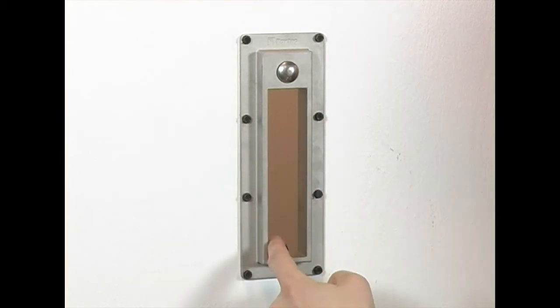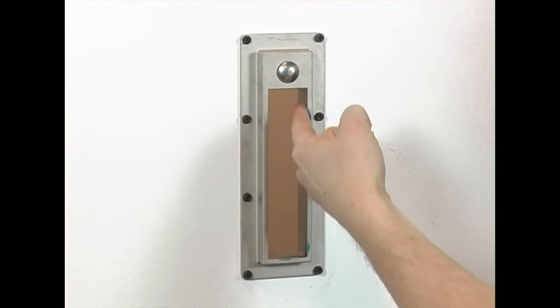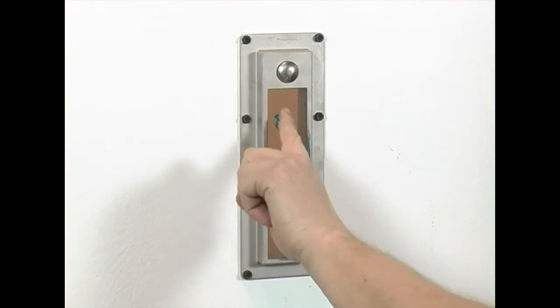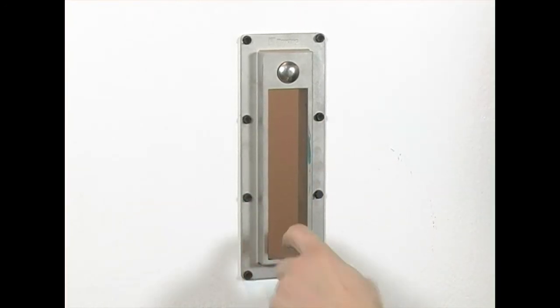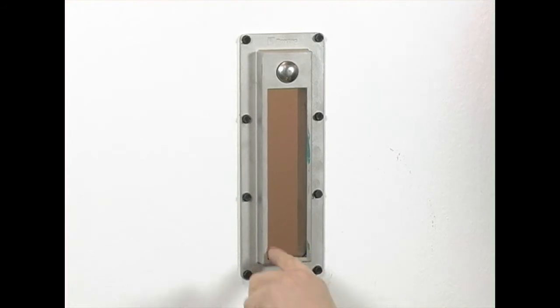Lubricate the inside of the frame with Roxtec assembly gel. Do not lubricate where the foil is to be situated, 15mm on the back side of the frame. Make sure that you lubricate the corners.